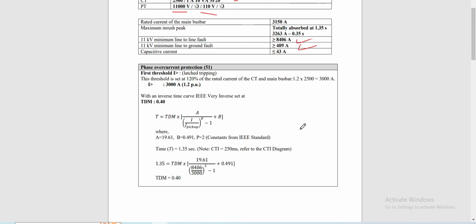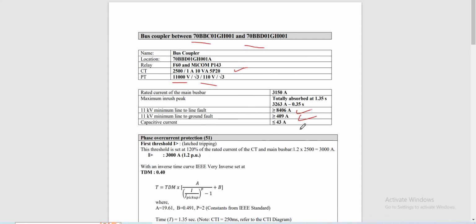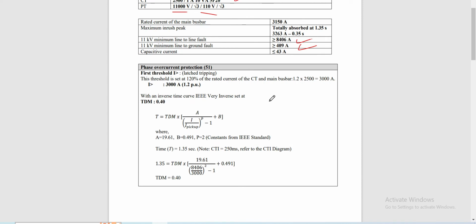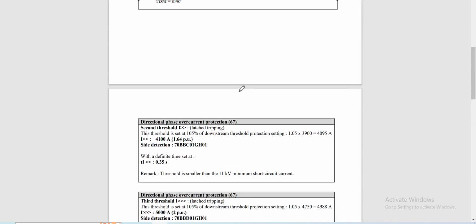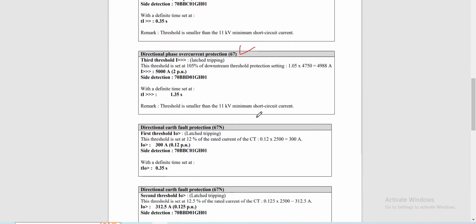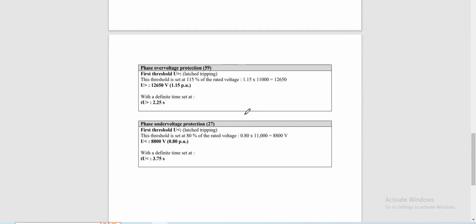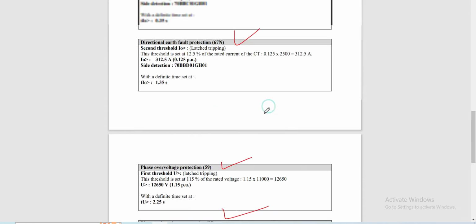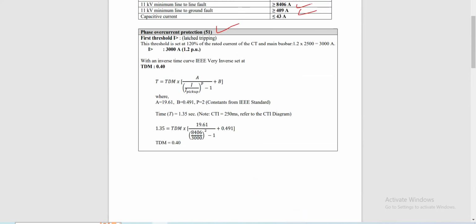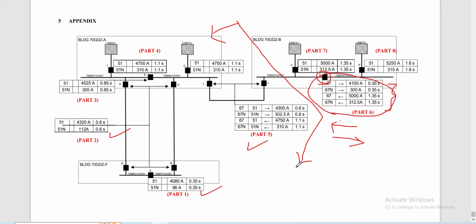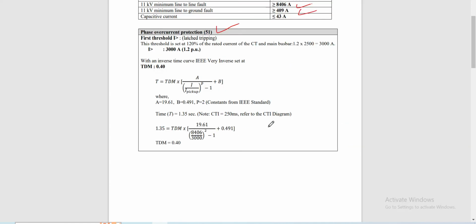Right now, we will be calculating the following relays: the 51 relay, the 67 relays here, also the 67N, the relay 59, and relay 27. So let's open this again. Anyway, what is mentioned right now in our bus coupler is only the directional relay, but if you refer to our calculation, we have also calculated the ANSI 51 relay.